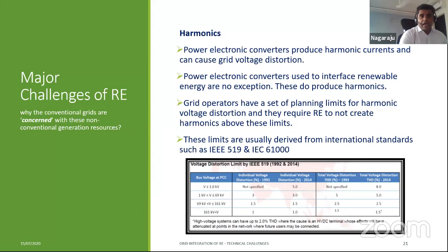Then power quality issues. I'm not touching on the voltage dip or flicker because there's a bit too much technical detail. But one thing that people are very much aware of is the harmonics. The power electronic converters do produce harmonics. They inject harmonic currents, and the power electronics interfacing renewable energy are no exception. And the grid operators have a set of planning limits. A lot of them are country specific, but mostly derived from international standards such as IEEE 519 or IEC 61000. IEEE is mostly followed in America as well as in India, whereas IEC is mostly Europe centric.